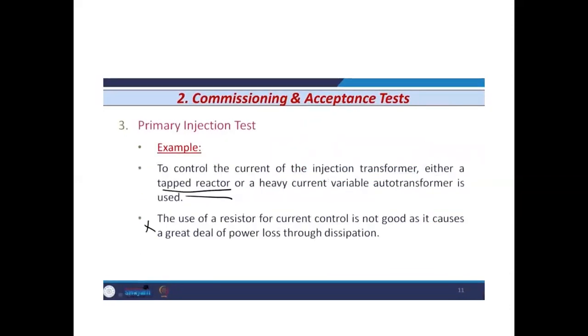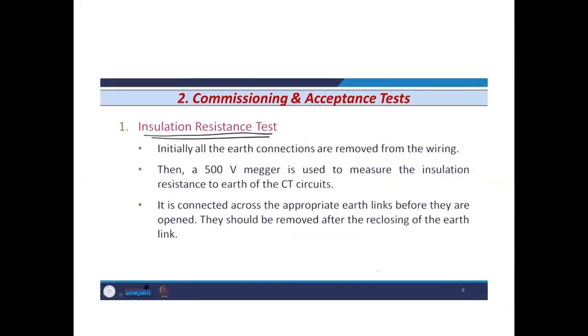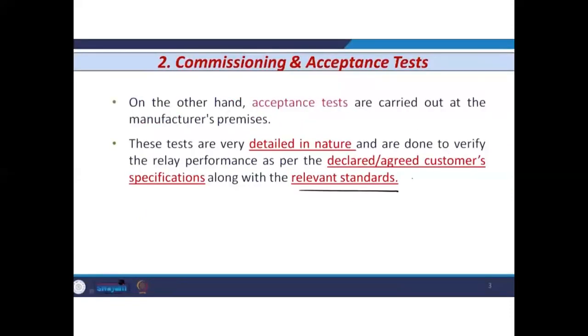In the previous class, we discussed the type tests, the different type tests. Some of the tests were applicable for electromagnetic relays and some for static relays. Now this is the second type of test, the commissioning and acceptance tests. Acceptance tests are carried out at the manufacturer's premises. In the previous tests, most of the tests were performed on the manufacturer side, and similar is the case here.